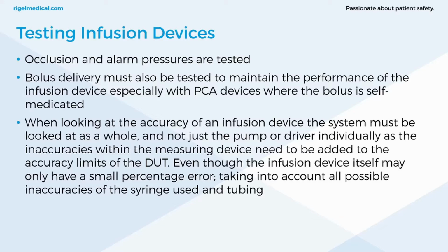So when looking at the accuracy of an infusion device, the system must be looked at as a whole and not just the pump or driver individually, as the inaccuracies within the measuring device need to be added to the accuracy limits of the DUT, the device under test. So we're looking at all the possible uncertainties within the system. It's not just the device on its own.